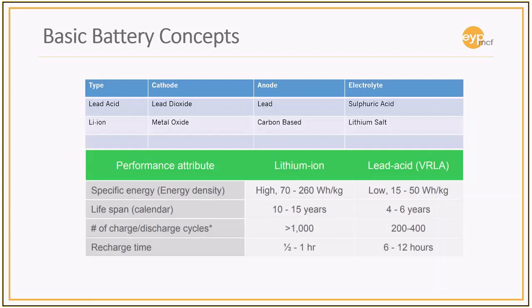Some different performance criteria or requirements around lithium-ion versus a lead-acid battery: the specific energy is much denser, much higher in a lithium-ion configuration. They last longer, and they're okay with battery charge-discharge cycles. Ideally, you don't want to hit your batteries or discharge them unless you have to. So if you have poor power quality in your facility and you're hitting your batteries on a regular basis, lithium-ion is a better technology to use because it can withstand more cycles, whereas lead-acid batteries don't like to see that many cycles.